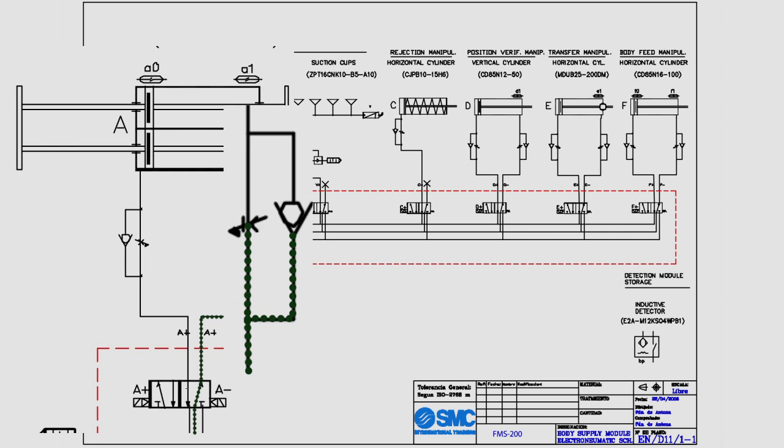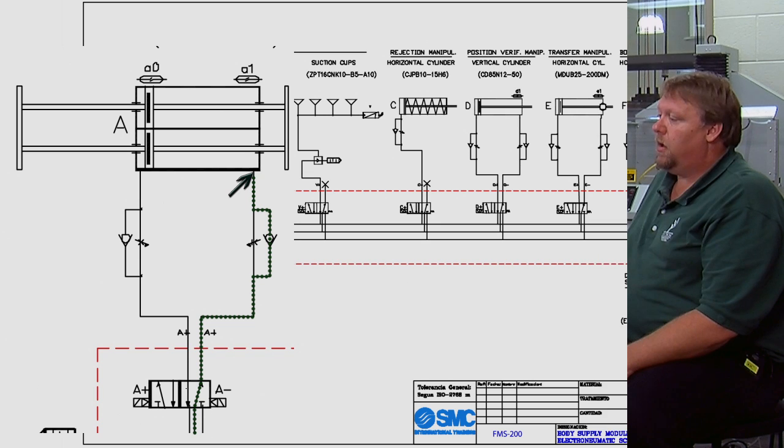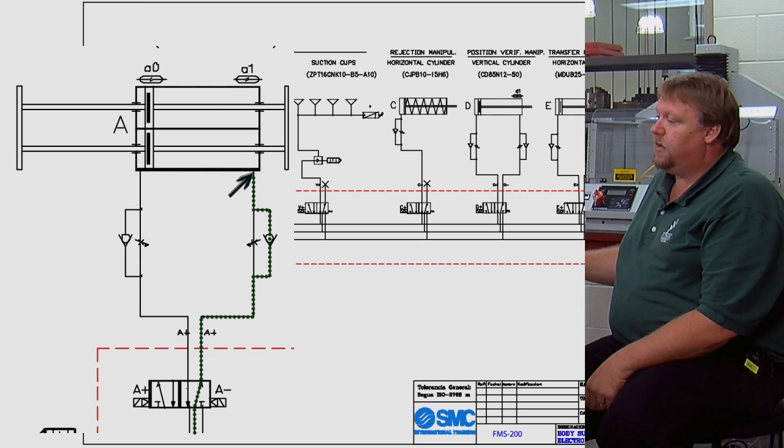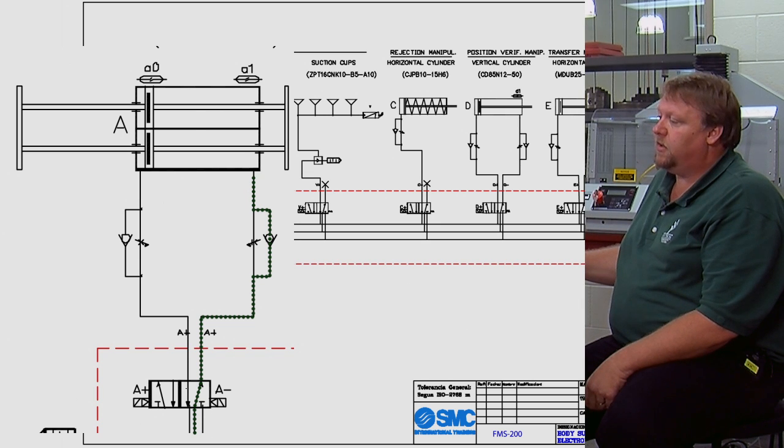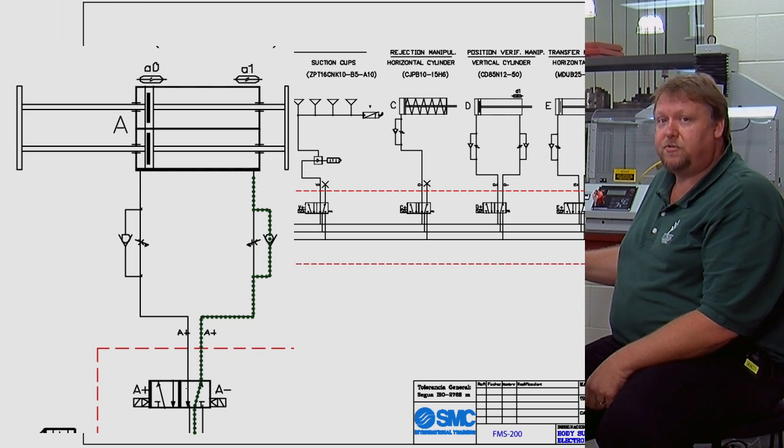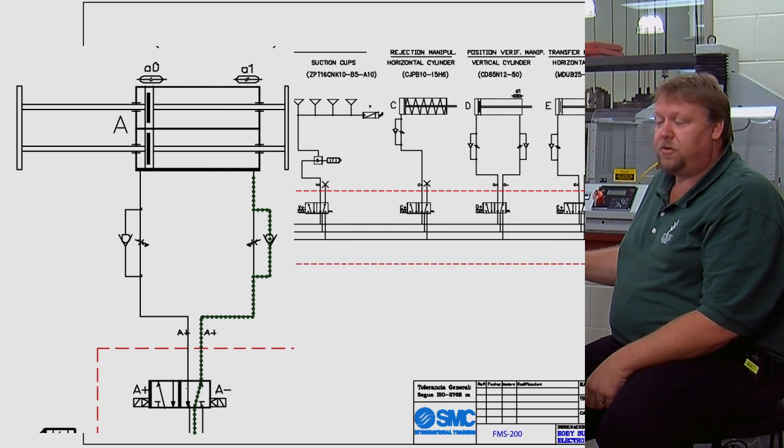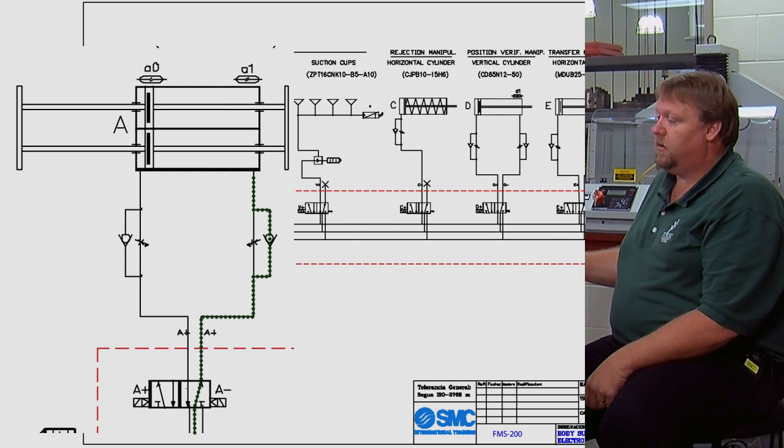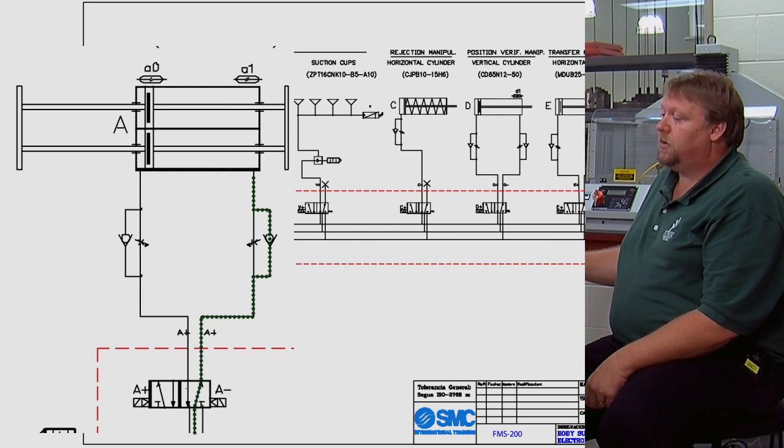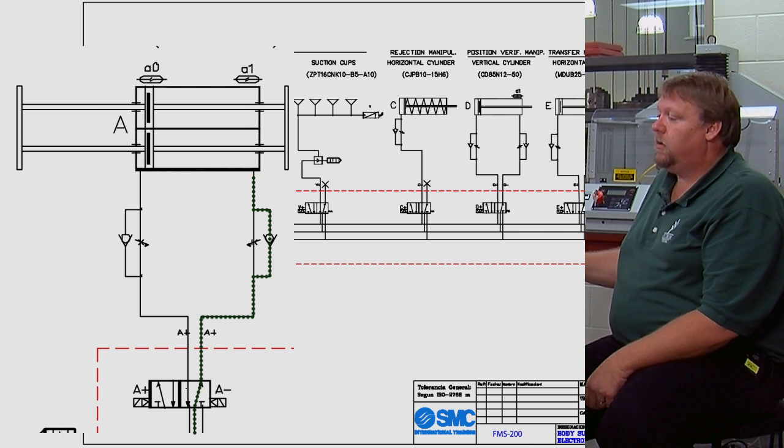So we have a restricted orifice right here and the next one we have a ball and seat. The air is typically going to want to blow the ball off of the orifice because it would require much more energy to go through the restricted orifice. So it takes the path of least resistance. We blow the ball off of there. We have air that enters the cylinder cavity right here. And when that does it will force this cylinder to extend. So as you can see that's why it is drawn in this formation right here with this cylinder actually being extended. This is the normal position of this valve.